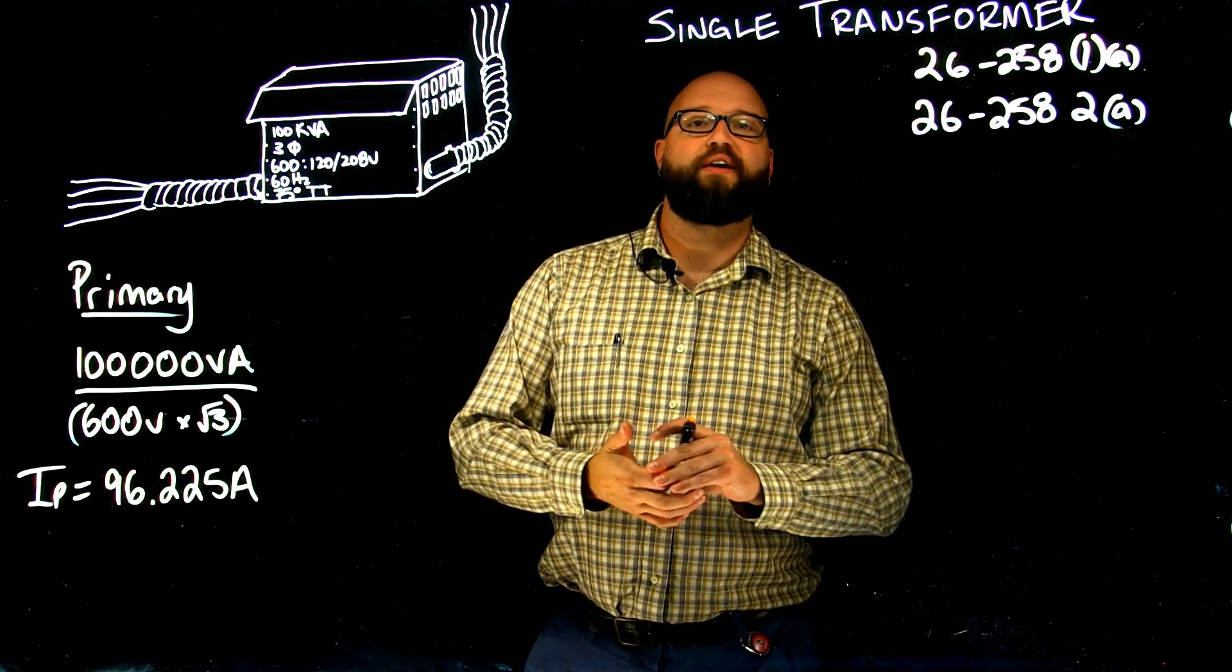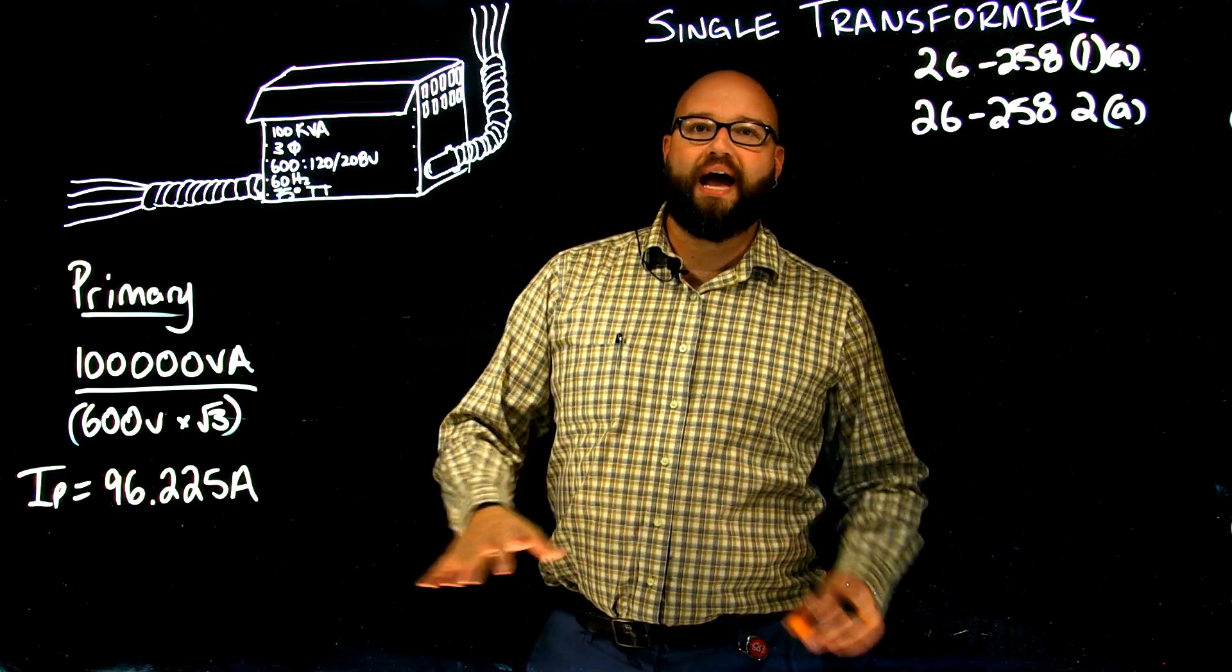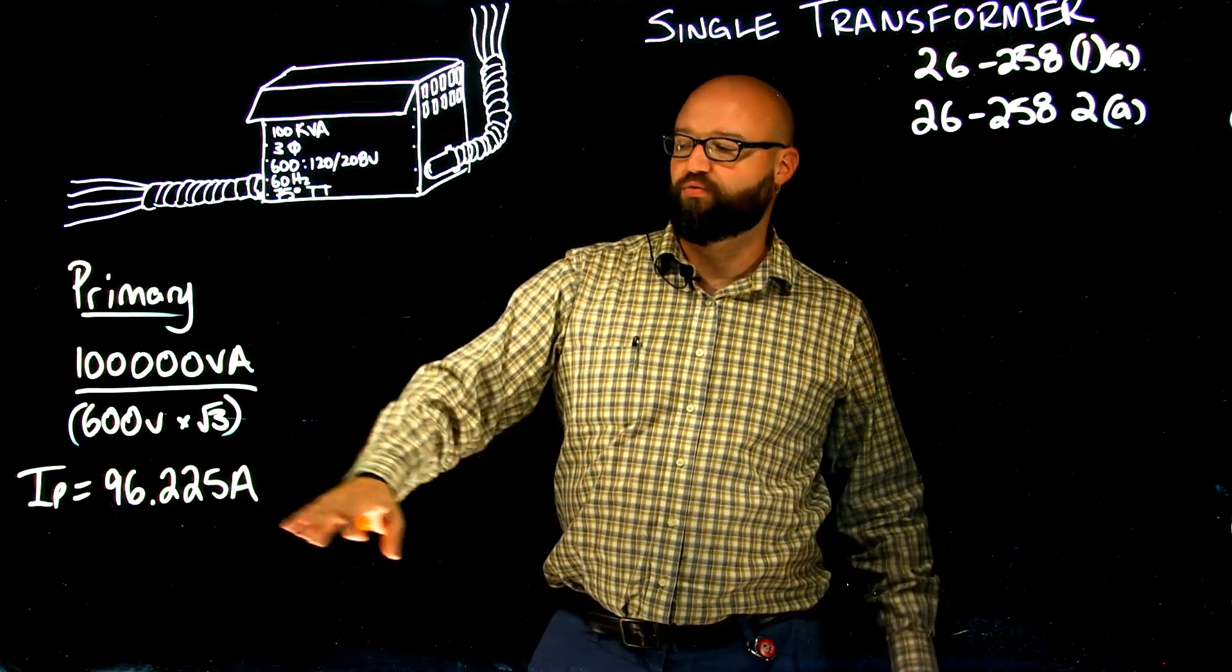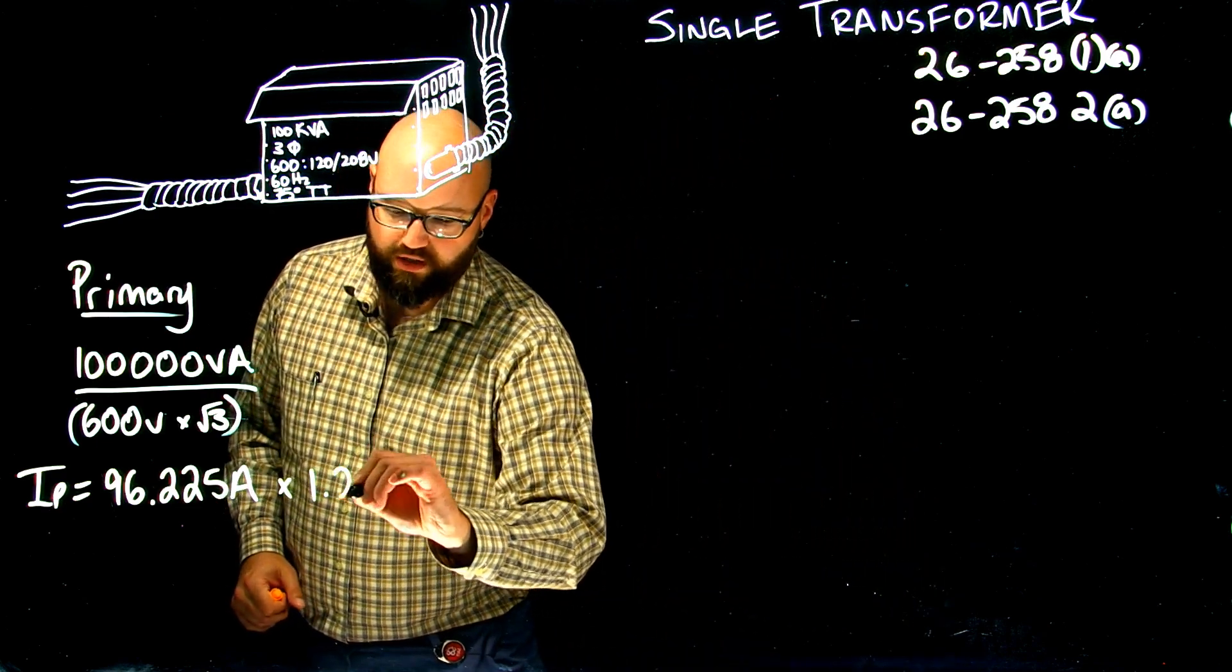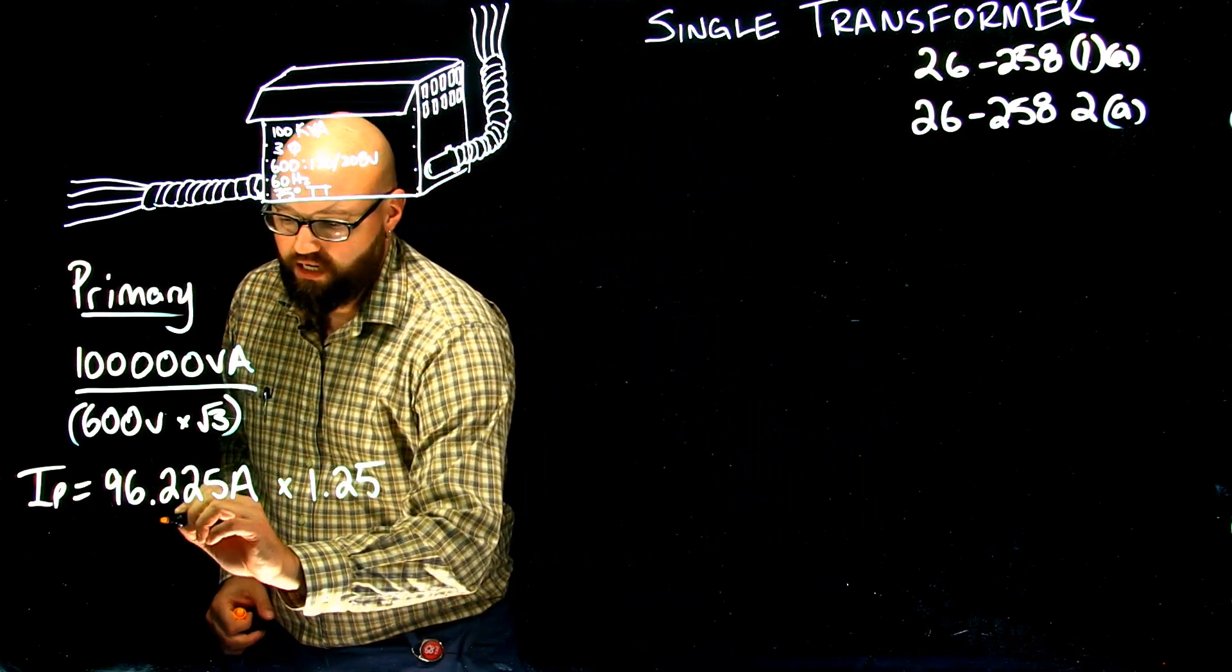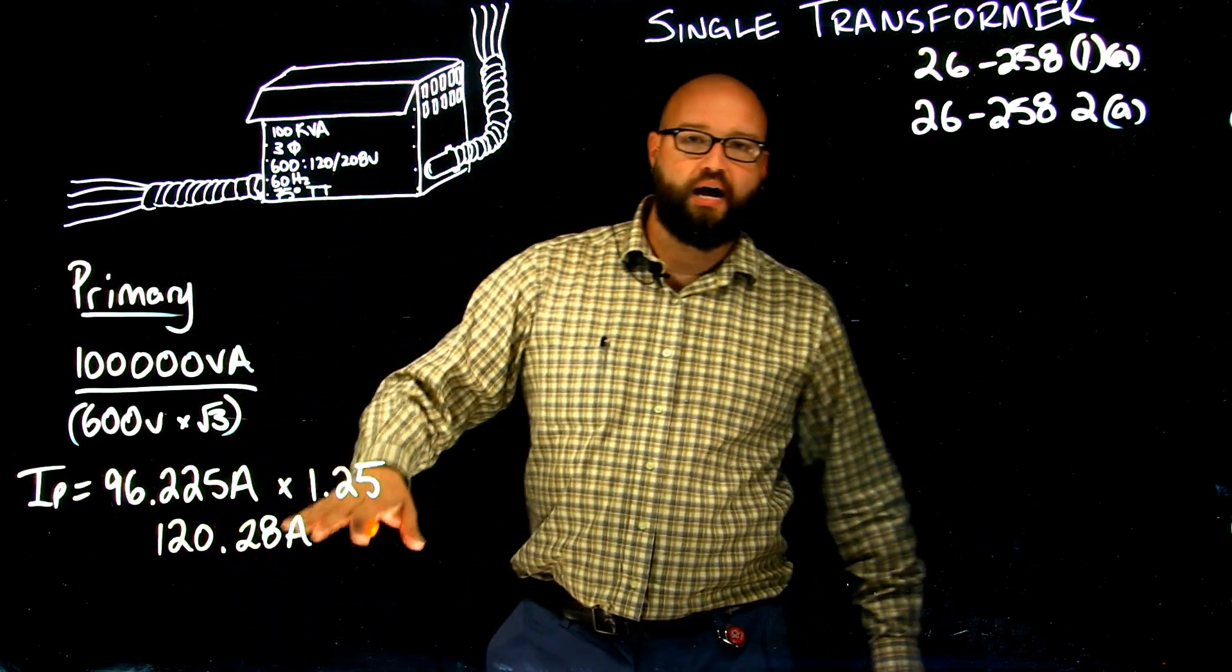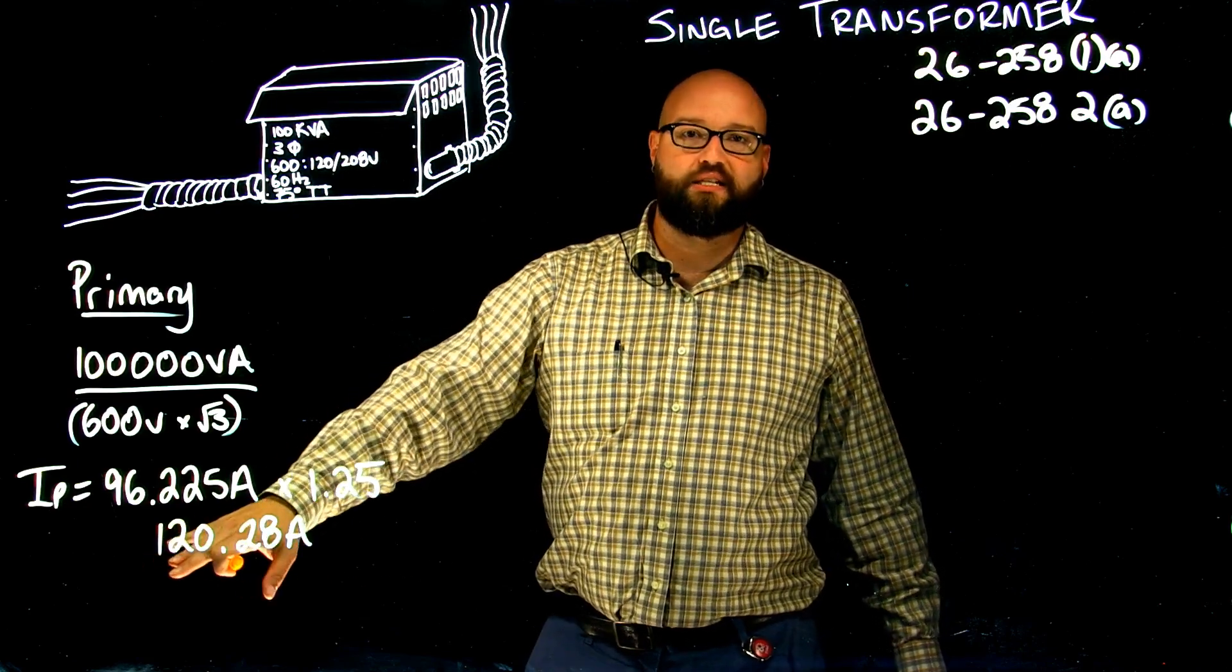Now, what it tells me in 26.258.1A is that my conductor ampacity has to be at least 125% of this number. That means we have to be at least 1.25 times greater than that rated primary. So, times 1.25 gives me my minimum ampacity of my conductor, and we should see 120.28 amps. I know that I have to pick a conductor with an ampacity of at least this number.